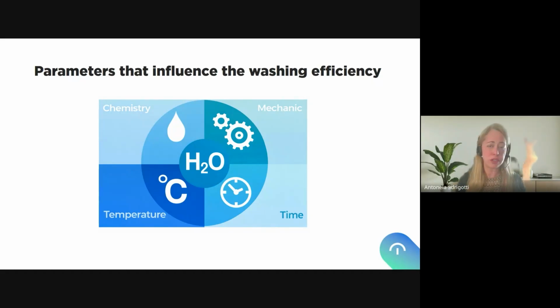In the center, water. When we talk about water, we are talking about the quality of the water. Not every water is the same, even if we just say water. We have to pre-treat the water that we are going to use in the washer. Some regions, some countries still don't use pre-treated water during the full cycle. It is only mandatory to use pre-treated water for the last rinse before drying. But if we use pre-treated water during the full cycle, we make sure that we preserve the instrument, we preserve the machine, and we preserve the performance of the detergent that we are using, because everything that is dissolved in the water will influence all of this. So preservation of instruments, washer, and performance of the detergent is guaranteed.